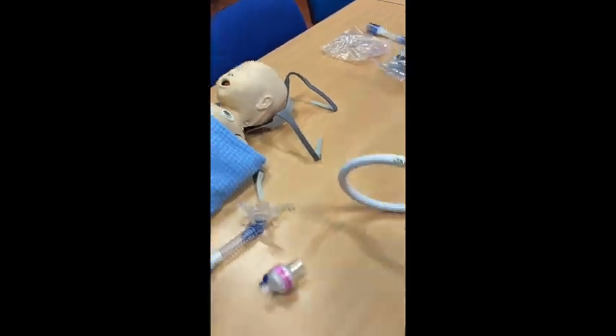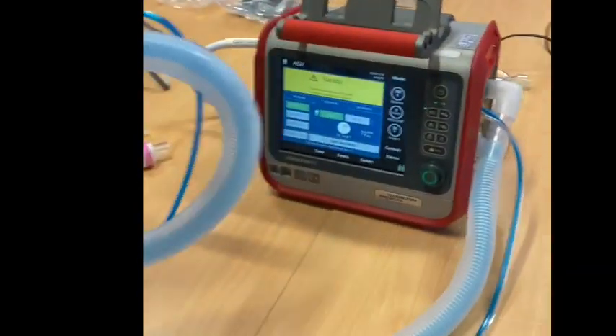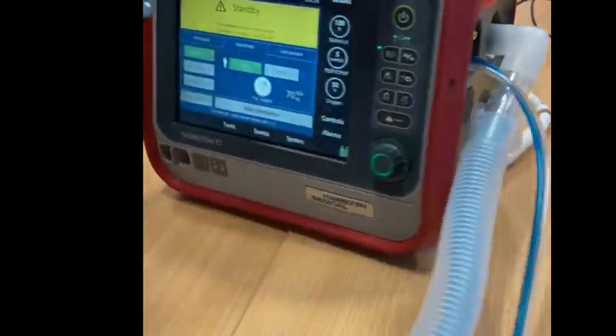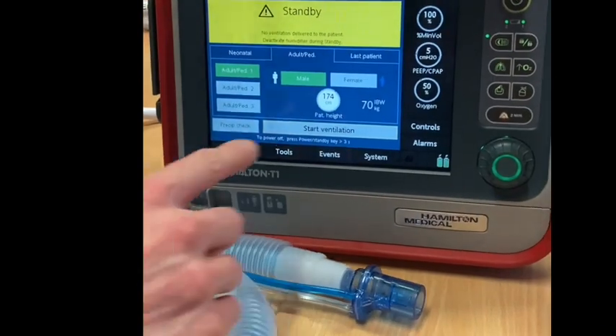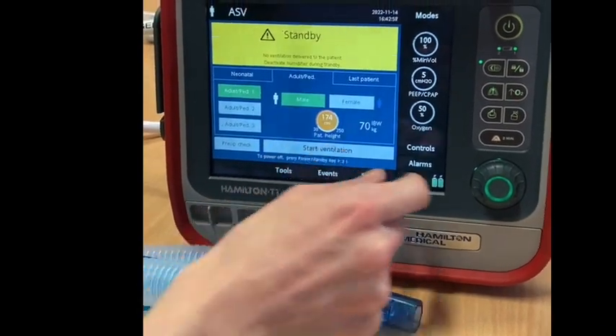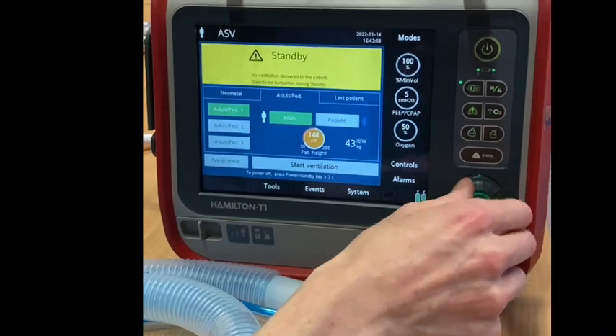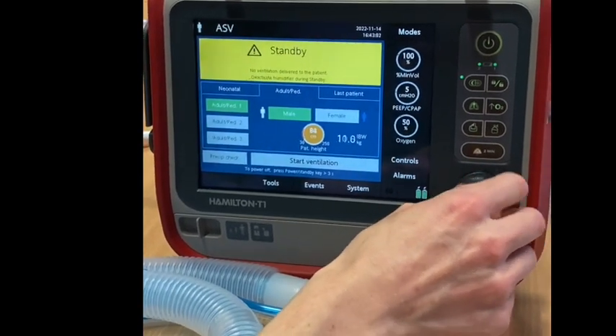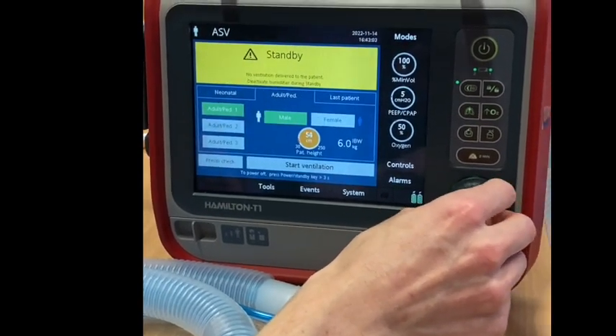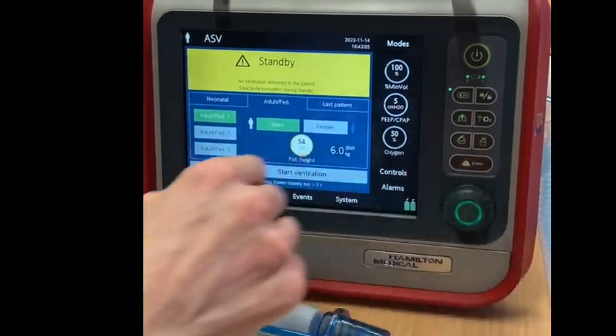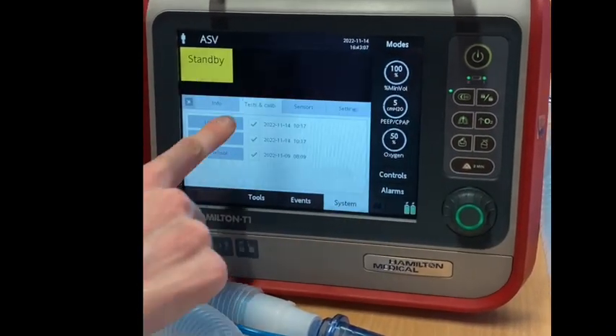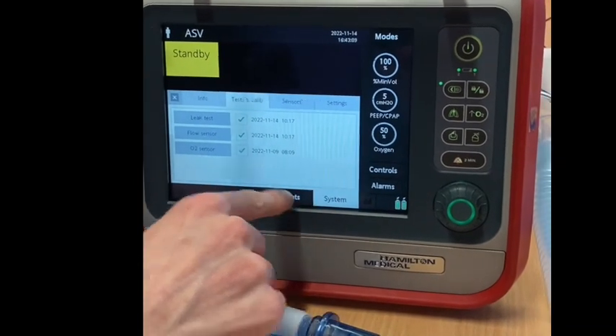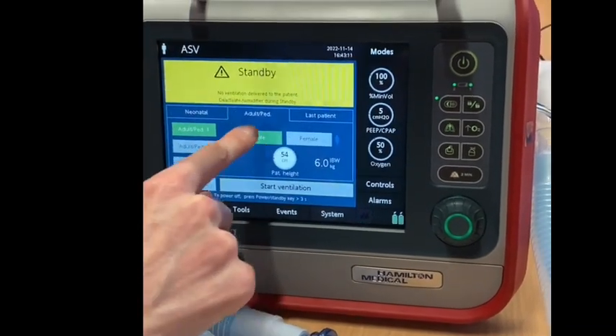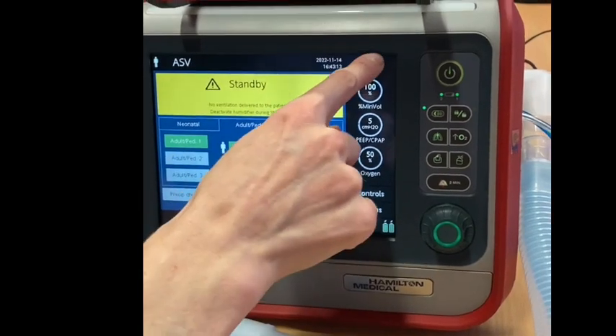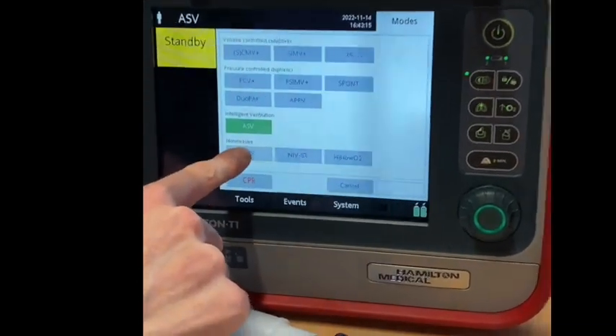We also generally recommend setting up the head gear in advance of commencement of CPAP. Please set the vent as you normally would from a tubing perspective for adult ventilation. Make sure you're in adult PED mode regardless of the weight and age of the child, and select the required weight. It's important to make sure that all pre-op checks are done, including the flow sensor check. And finally, go into modes, select NIV.